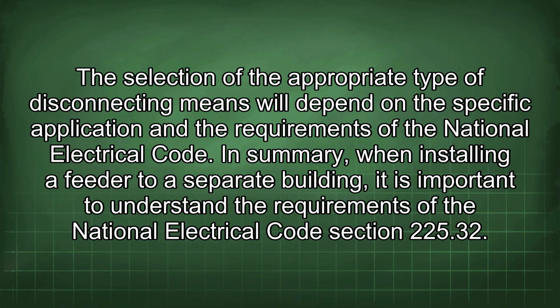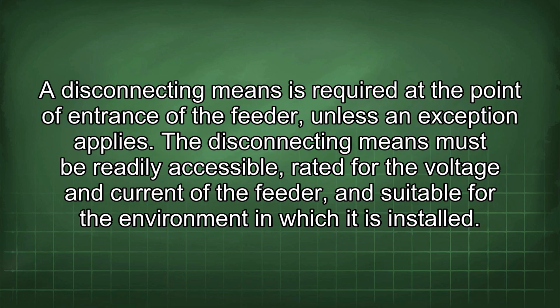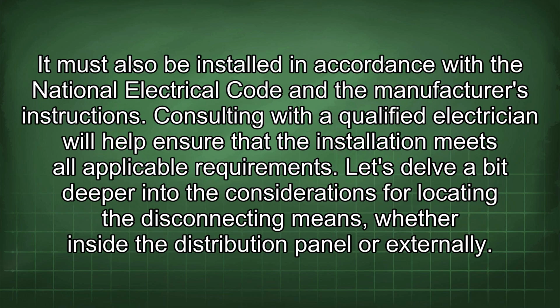In summary, when installing a feeder to a separate building, it is important to understand the requirements of the National Electrical Code Section 225.32. A disconnecting means is required at the point of entrance of the feeder, unless an exception applies. The disconnecting means must be readily accessible, rated for the voltage and current of the feeder, and suitable for the environment in which it is installed. It must also be installed in accordance with the National Electrical Code and the manufacturer's instructions. Consulting with a qualified electrician will help ensure that the installation meets all applicable requirements.